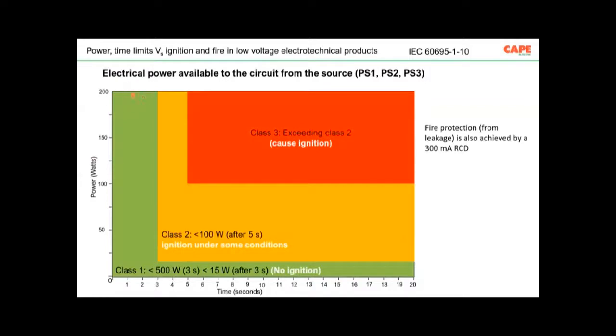So this particular power, irrespective of the maximum limit, where I have put 200 watts as the maximum limit, actually it's irrespective of the maximum limit. If the fault is reduced to less than 15 watts within 3 seconds, that is, the fault energy is reduced to 15 watts, this is called power supply class 1, which is not supposed to ignite a fire. This kind of power supply is not supposed to ignite a fire under normal conditions. Power supply class 2 means a power supply which is reducing the fault to less than 100 watts within 5 seconds. Under this condition, ignition is very much limited. Ignition is not so common. Power supply class 3 can ignite fire.